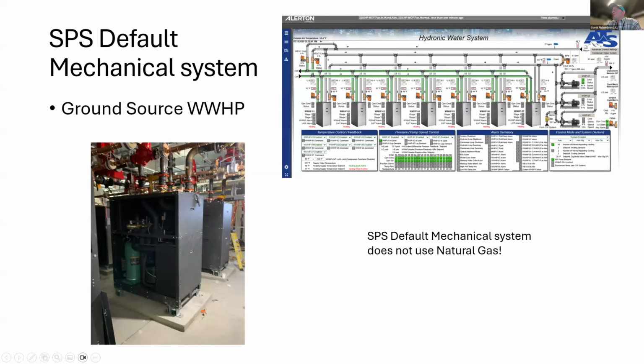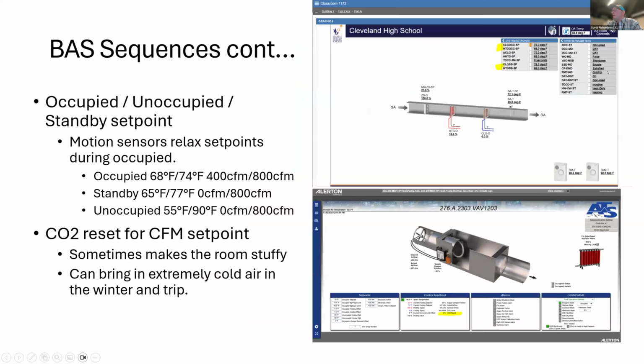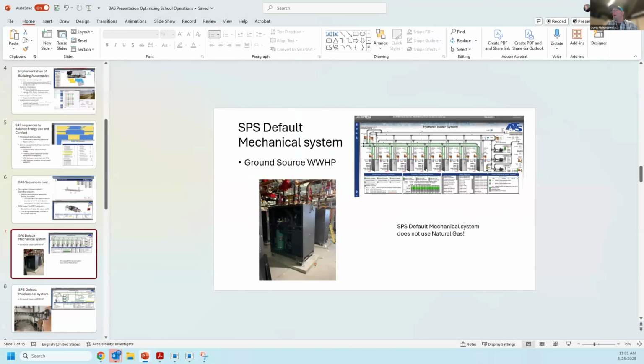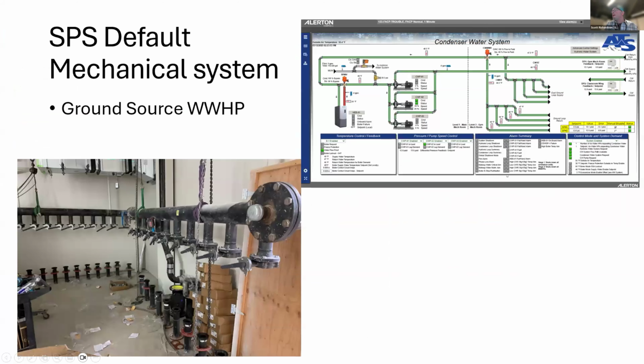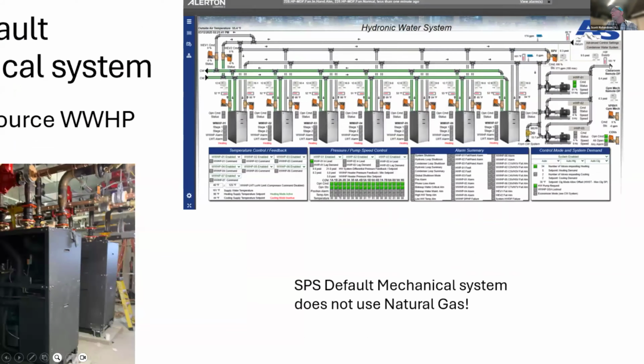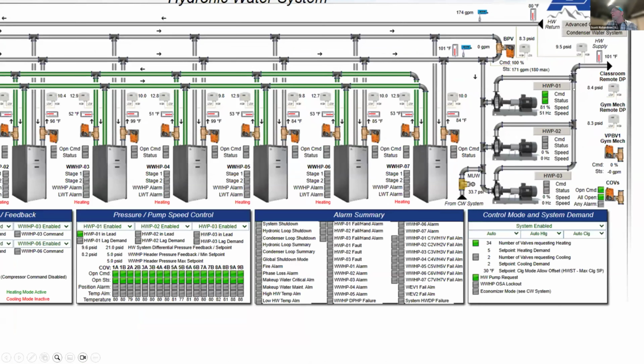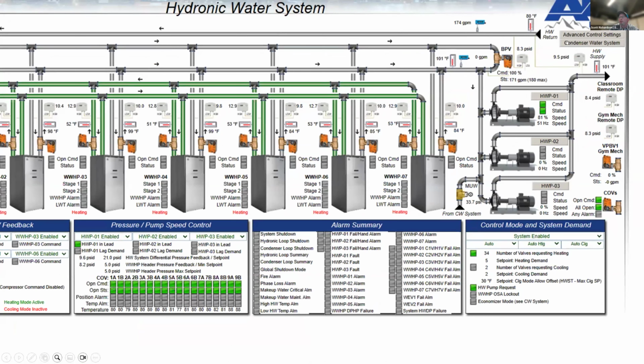You've got your 2 loops on the water-to-water. You've got a condenser water side and a hydronic water side. The hydronic water side runs out to the building. You've got 101 degrees going out and 80 degrees coming back, so that's a pretty good delta there, 20 degrees.